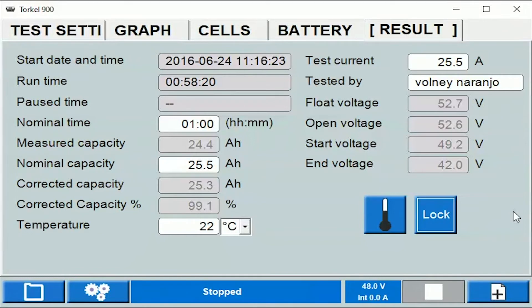Because we follow this sequence, the Torkel and the BVM are able to measure the battery voltage in the float condition. Then when the charger is turned off, they measure the open voltage of the battery bank. Eventually when you start the test, they log the first reading when the test is started.